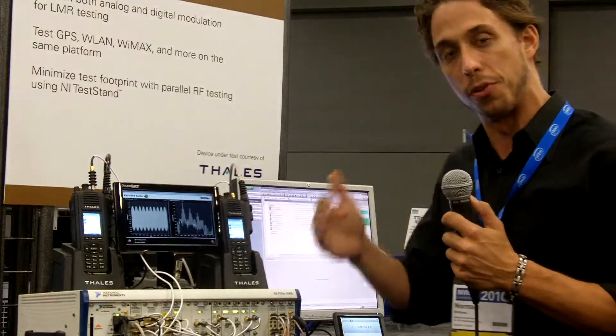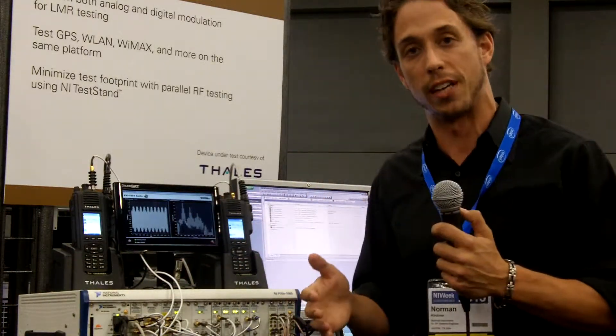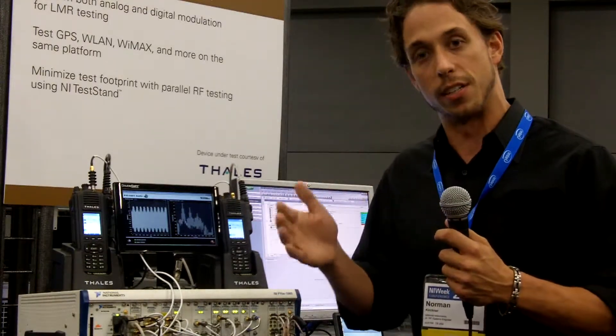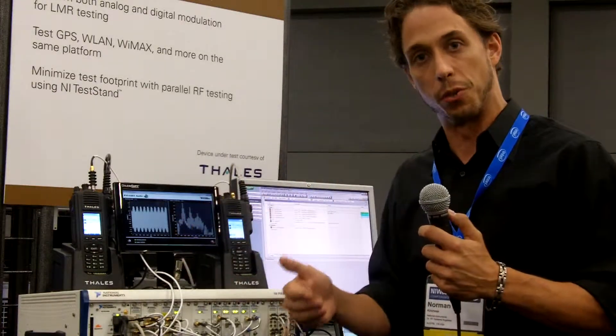What we're utilizing is TestStand in the background to actually execute both units at once, and a variety of switching in PXI utilizing our switch executive, which automatically takes care of arranging the tests and determining which radio goes into transmit tests and which radio goes into receive tests.